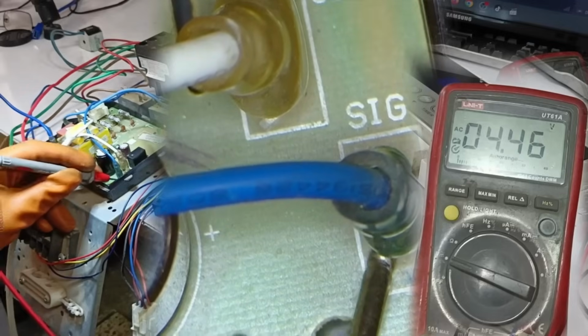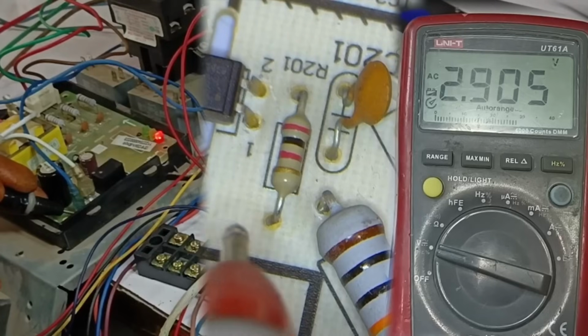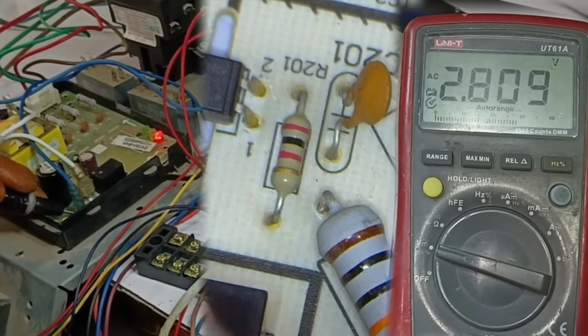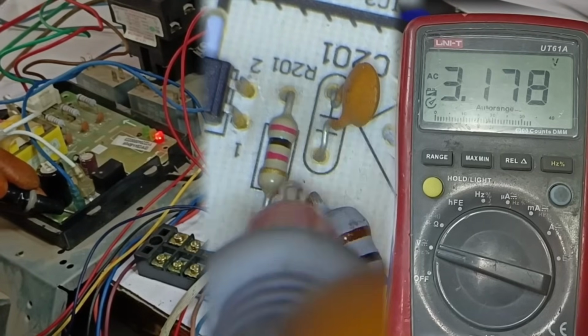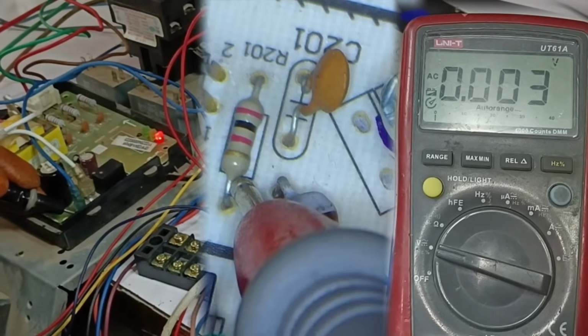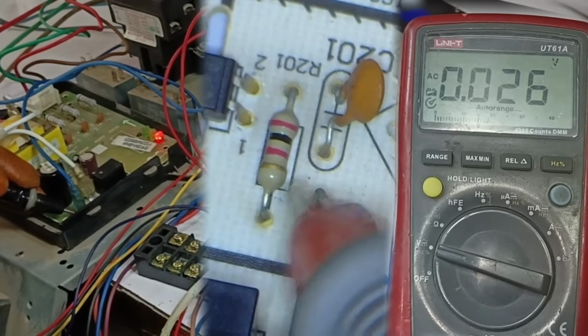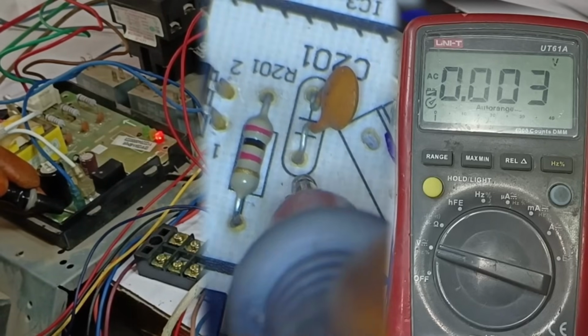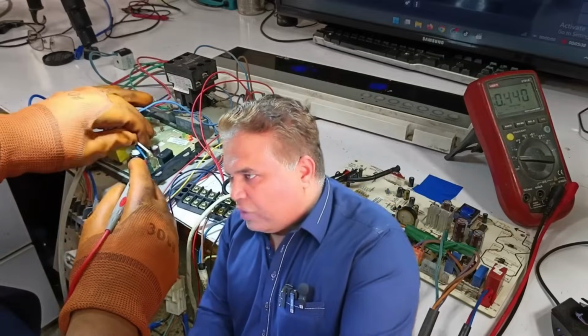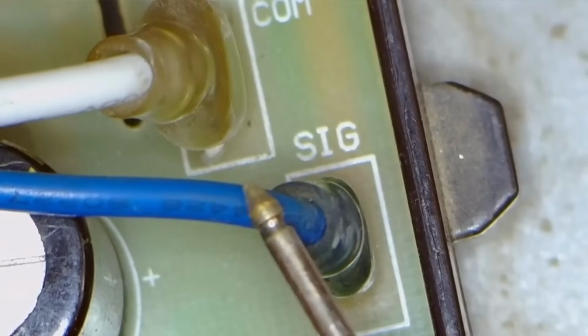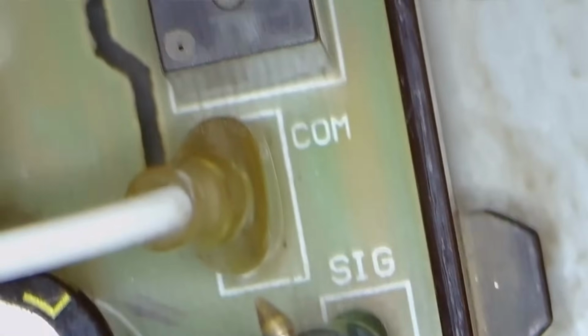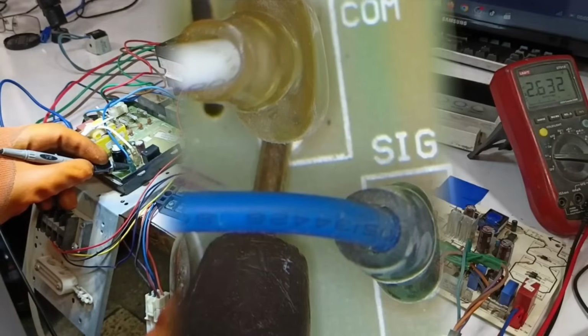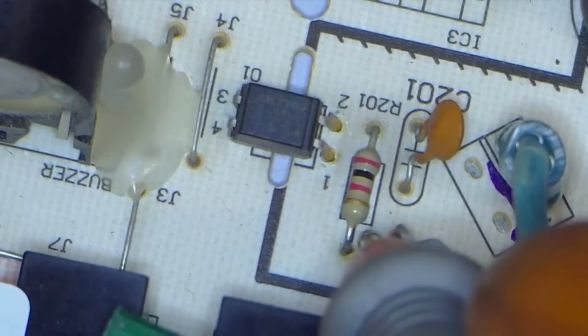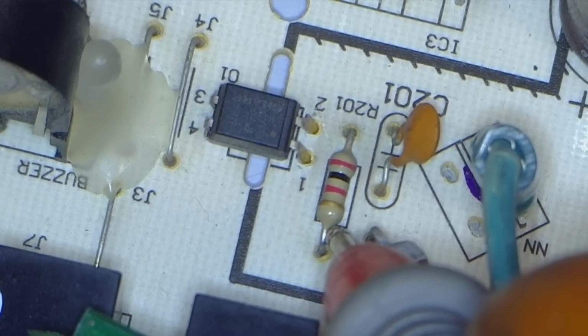I placed one multimeter probe on the signal point and the other probe on either side of this resistor. As you can see, it is showing 0 volts here. Now let's check the other side of the resistor. Again, there are no volts appearing. This means that our neutral is not functioning at all. Now what we will do, since the neutral signal is not reaching up to this point, is move to the common point. I will place one multimeter probe on the common and the other probe on this resistor to check. As you can see, we are getting 90 volts here.